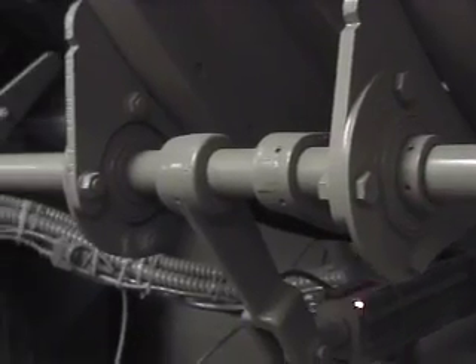As you don't need the capacity, these vanes will start to shut back down, and the motor speed will drop back down. Usually, in a running condition, they run 45 to 53 hertz, more or less, of the 60 hertz. Other than that, I think that's everything we've covered. Do we have any more questions I can answer?